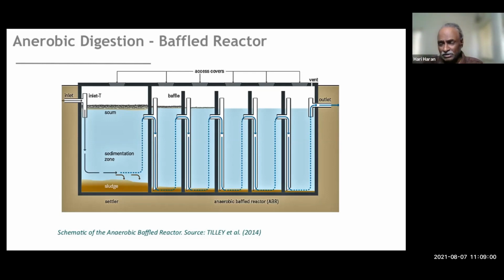Depending upon what the technology is, they will decide what the sizing of each of these things will be. That last tank has not yet come there. The settlement tank will be the one that is critical for him, and the aerator tank, the third tank. Now, what happens to you, therefore, is if he says 1 lakh liters is 2 lakh liters for you, 2 lakh liters into 15, that is 30 lakhs of your money. Now, if he says, no, I can manage with 1.5 lakh liters instead of 2 lakh liters, then your civil works cost is going to fall as much.